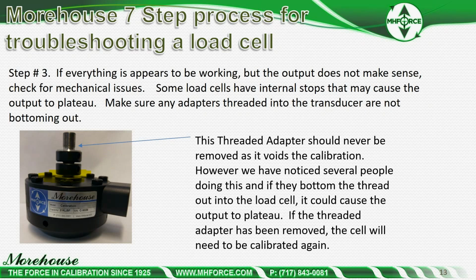Lots of people like to take these in and out. What will happen is if you don't get this in right, you can plateau it. You can actually run the threads completely down until you hit the compression stop, and if you do that and then screw the nut back in or torque the jam nut back in, you'll have a situation where eventually the load cell will plateau. So we have noticed several people doing this, and if they bottom the thread out in the load cell, it could cause the output to plateau.